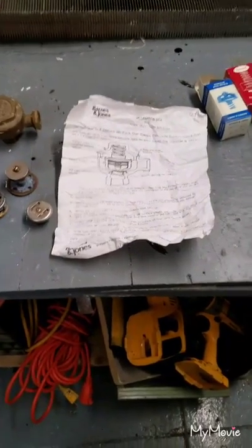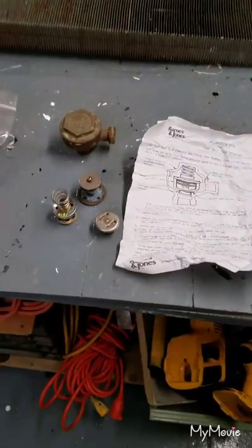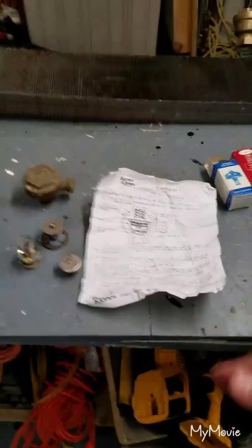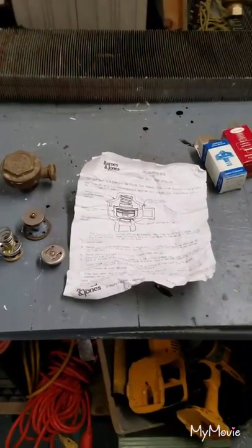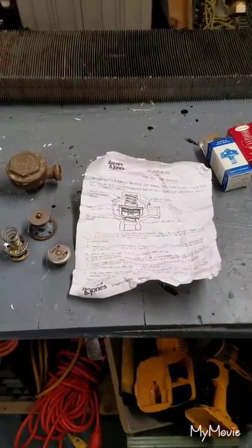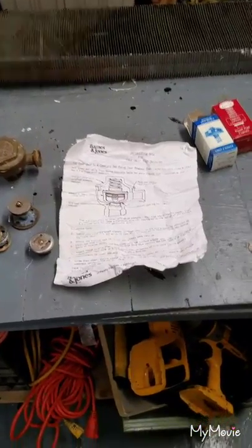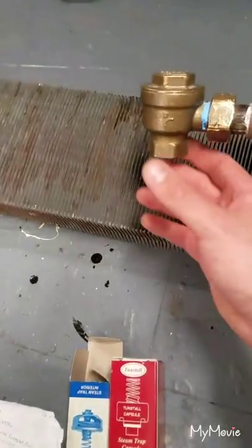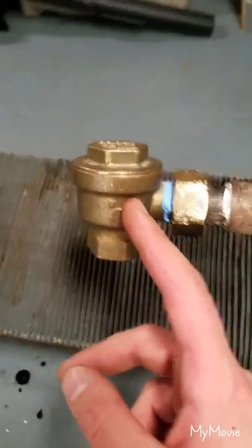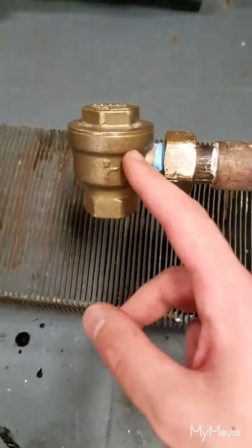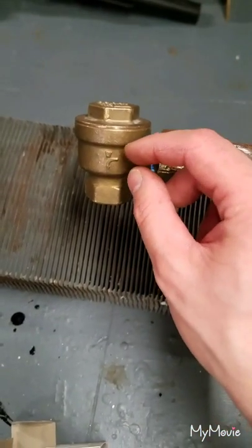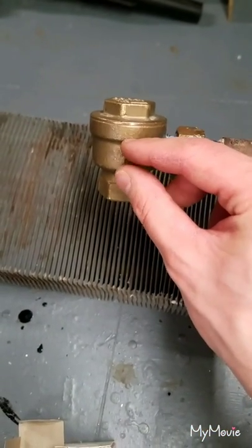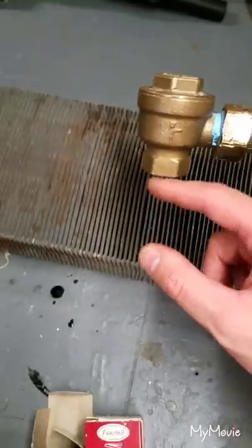Hey guys, so now I wanted to talk about some of the traps on the radiators. I'm going to talk about the traps on the radiators, and then I'm going to go into the main traps that you will find off the steam risers, return risers in a building. Okay, so first, here's that radiator I showed earlier. This is a Sarco trap. So when the steam comes into this trap, there's an element inside, and when the steam comes, the element expands when it heats up and it lets the condensate drip out.